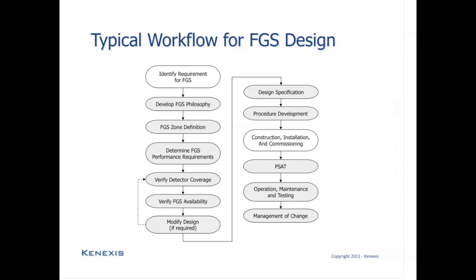Now, what was shown to you previously was the safety life cycle as presented in the TR 84.00.07 technical report. And the way that life cycles are written in the technical reports and in the standards is really more of a placeholder for the requirements for the various sections and phases of design. And those safety life cycles should never be used as a flow chart for how to actually execute a project, because that was never their intention. The intention of those life cycles is a structure for listing requirements as opposed to a procedure for executing a project. What I'm presenting in this slide is more of a procedure for executing a project or a typical workflow for a performance-based fire and gas system design.